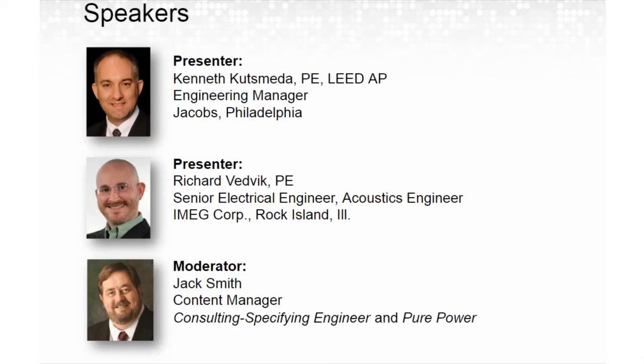Okay, Ken, next question is for you. Are DC building electrical distribution systems being implemented these days? And if so, how often? So we are seeing, in the data center field, some data centers going to DC. As I said, most of the server components are DC-based. So when you look at the UPS system, you go from an AC to a DC battery, then back from DC to AC, then transfer AC, then it goes back to DC. So every time you make that conversion, you lose power. So going from a UPS to a DC distribution will actually save you energy because you avoid those losses.